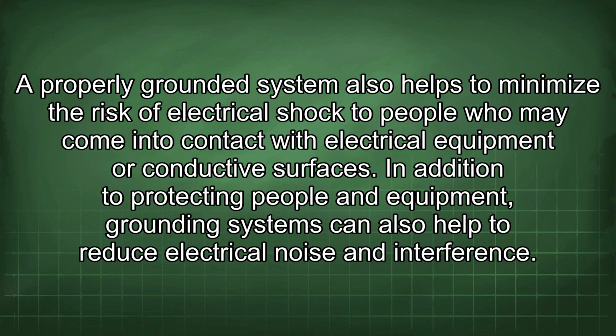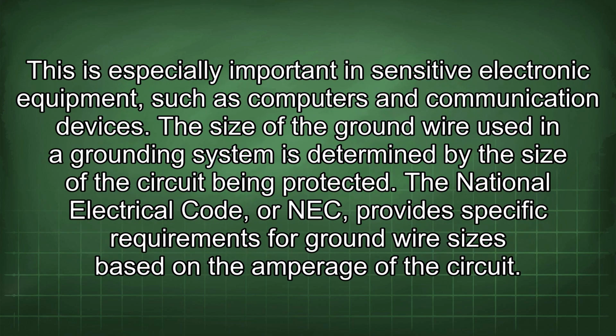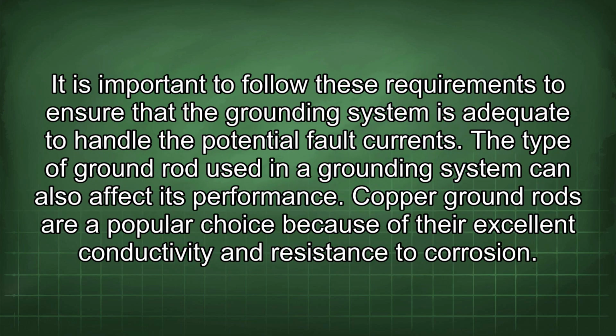In addition to protecting people and equipment, grounding systems can also help to reduce electrical noise and interference. This is especially important in sensitive electronic equipment such as computers and communication devices. The size of the ground wire used in a grounding system is determined by the size of the circuit being protected. The National Electrical Code, or NEC, provides specific requirements for ground wire sizes based on the amperage of the circuit. It is important to follow these requirements to ensure that the grounding system is adequate to handle the potential fault currents.